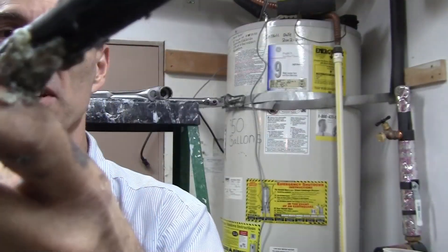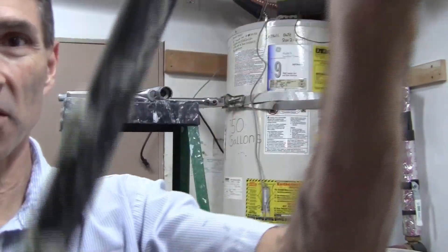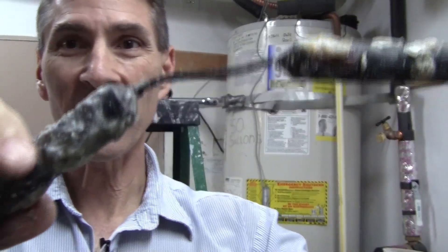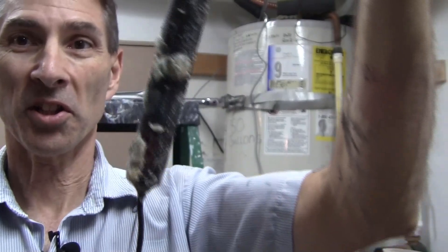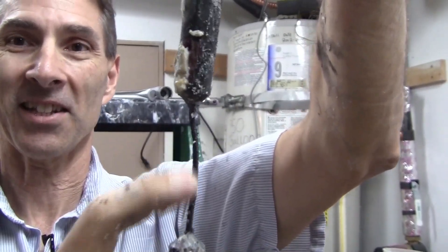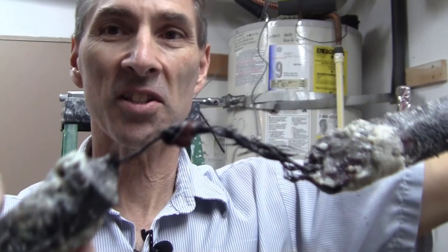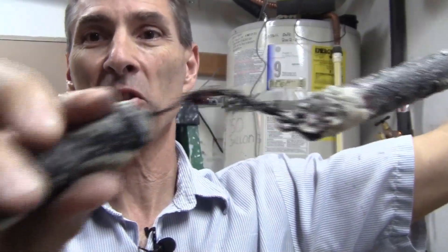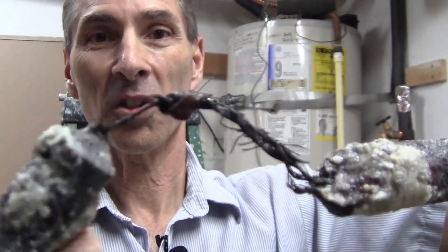Here is the existing rod after four years — there's tons of calcium and magnesium buildup on this. You can see where it's been wearing away. I've seen these things whittled down in other videos where they start off full thickness and get pulled out the size of a wire, so there's still a lot of material left on this one.